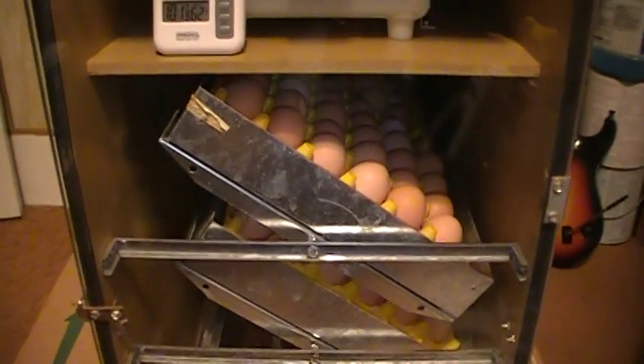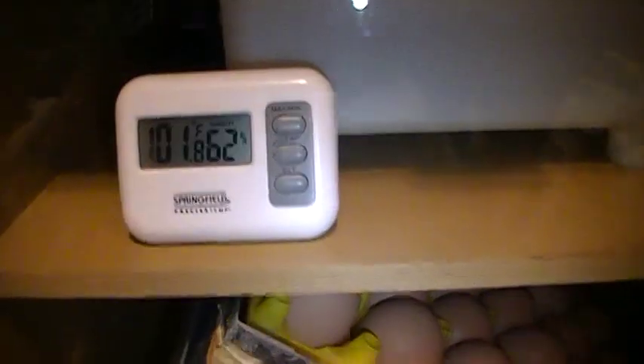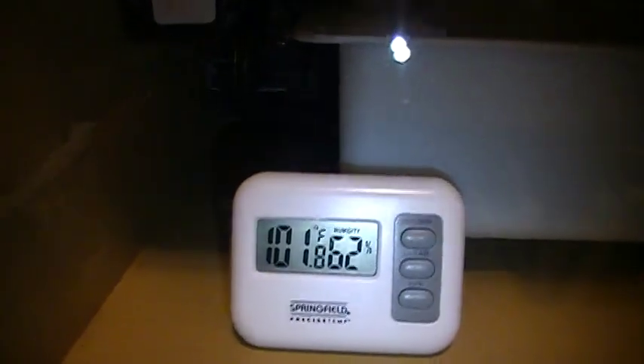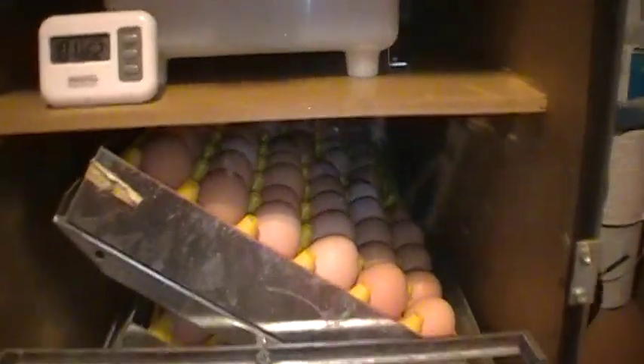And again, this shows, if you look last time, I'm at 101.8 degrees on my top shelf, but down here where the eggs are located, and I'll see if I can show you that probe. You can see the probe right there hanging right above my eggs. The temperature on the bottom of that shelf is 99.5. So we really don't care what the temperature is up here. There's no eggs up here to get overheated. Down here is where we need our critical temperature control. That's exactly what this unit is doing.